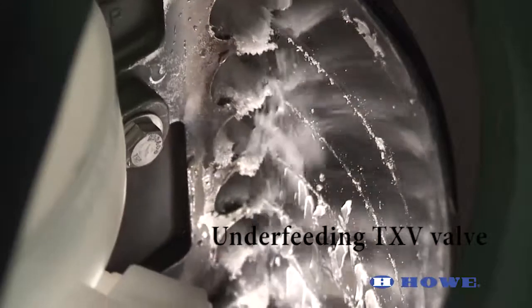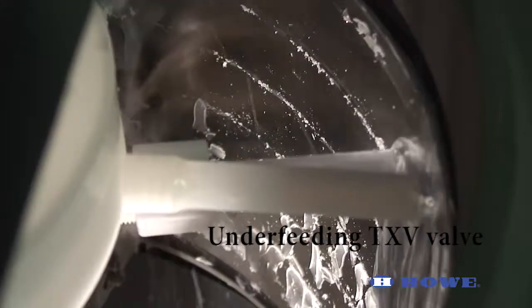Once you see evidence of underfeeding, open the expansion valve a quarter turn so that ice is again harvested on each rotation.